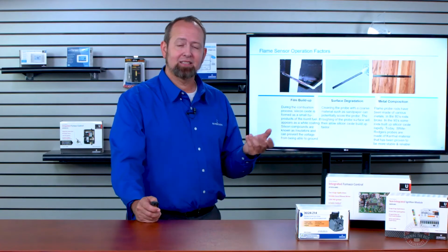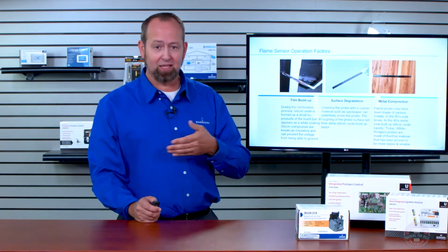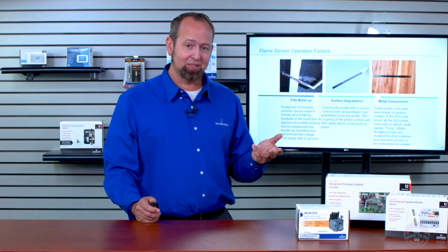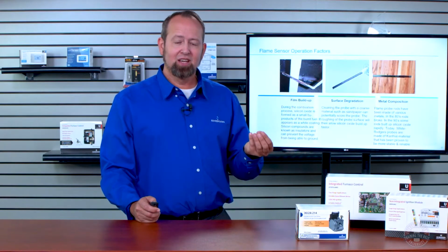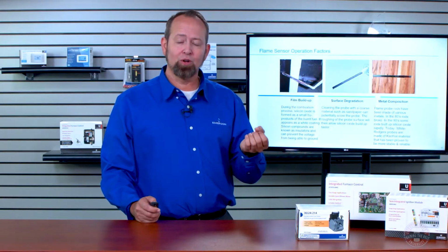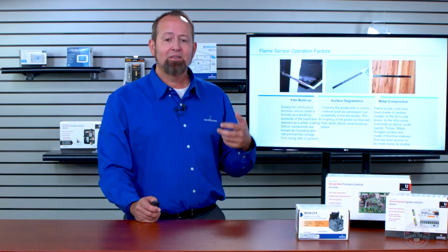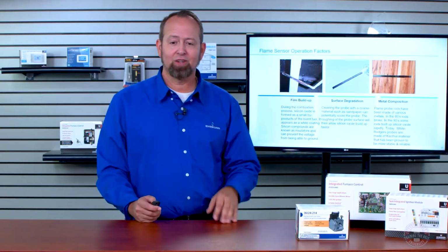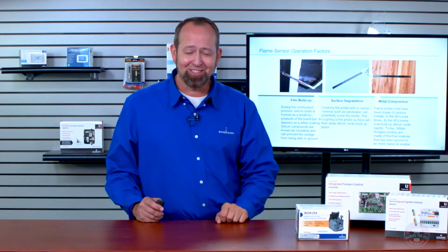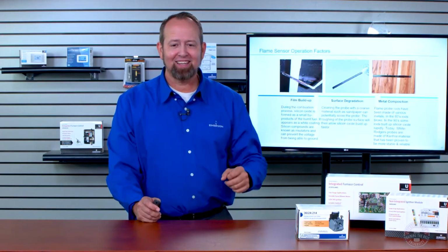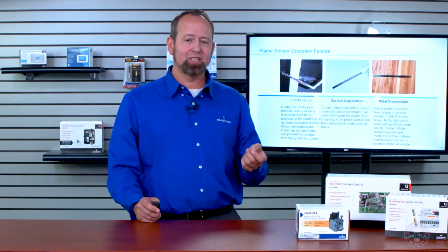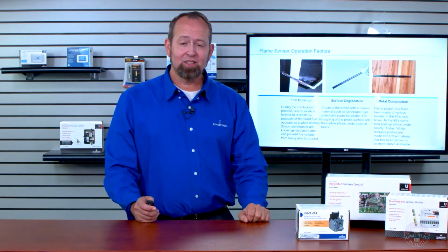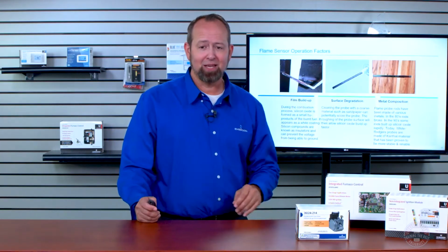In the 90s, as the composition of the metal was being tried and worked with, there were some of these flame sensors where the composition allowed them to grab a hold of and build that silicon oxide up faster. Today, White-Rodgers probes are made of what's called a Kanthal material. I'll explain that in the next slide. That material has been proven to be more stable, more reliable, durable, and can withstand heat better than the earlier versions.